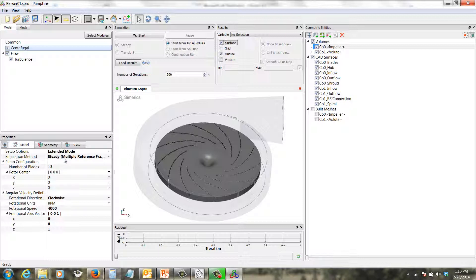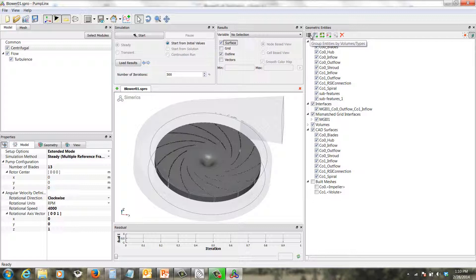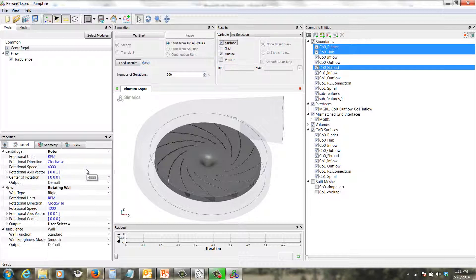We see that the impeller is rotating clockwise at 4000 RPM about the Z-axis. Similarly, the blades, hub, and shroud are rotating walls with the same specifications as the non-inertial frame. If you change one of these quantities, like RPM, in the centrifugal template, the rotating walls will be updated to include the new values automatically — so you don't have to change them in the rotating walls. The rotating walls serve to add momentum sources to the momentum equations so that the shear forces are accounted for. We see that the output for the rotating walls is power and torque.